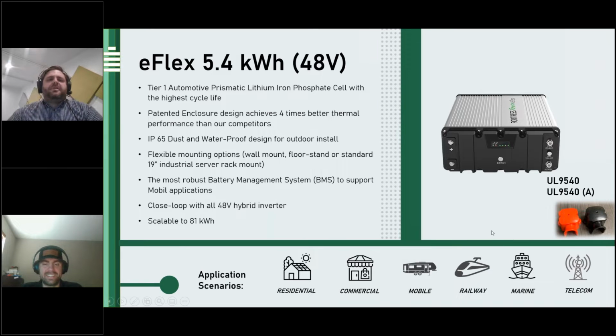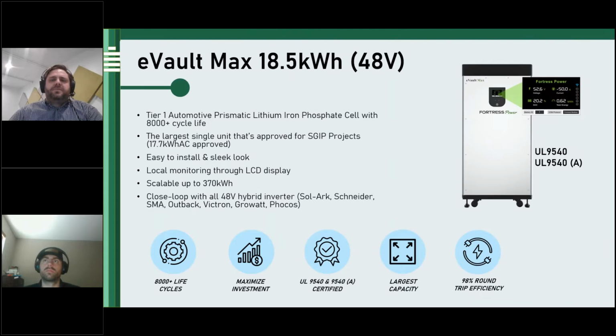The E-Flex battery is our more rugged battery. It's a little bit more compact. I call it the fighter because it packs a powerful punch. It has 5 kW of output for 5.4 kilowatt hour capacity storage. One kind of unique way that's used by many Sol-Ark installers is when you get into your minimum battery bank sizing. Typically with the eVault Max, it's 1 eVault Max per 1 Sol-Ark inverter. That's 18.5 kilowatt hours per Sol-Ark inverter.